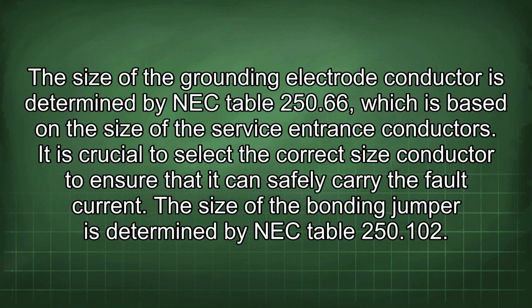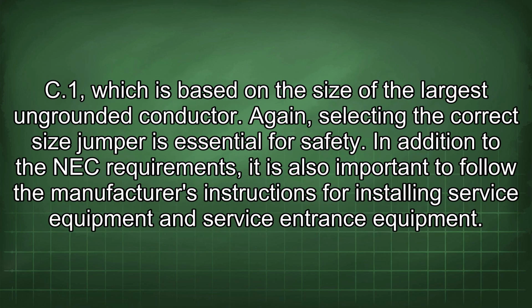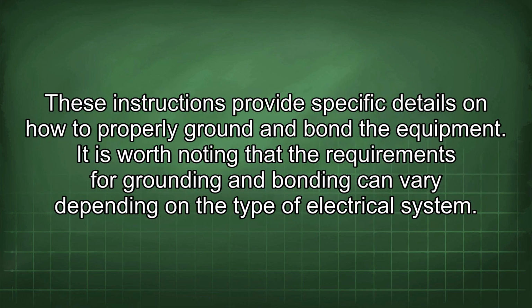It is crucial to select the correct size conductor to ensure that it can safely carry the fault current. The size of the bonding jumper is determined by NEC Table 250.102(C)(1), which is based on the size of the largest ungrounded conductor. Again, selecting the correct size jumper is essential for safety. In addition to the NEC requirements, it is also important to follow the manufacturer's instructions for installing service equipment and service entrance equipment. These instructions provide specific details on how to properly ground and bond the equipment.